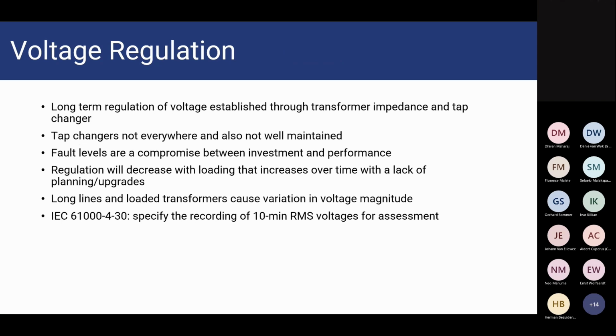Now, voltage regulation is the long-term regulation of the voltage established through transformer impedance and a tap changer. Tap changers are not everywhere and also not well maintained. And what also plays a big impact on your voltage regulation is the fault level at the point of measurement. And that's normally a compromise between investment and performance. So what do I mean by fault levels? On a system with a high fault level, you normally have a lower impedance, and vice versa, a lower fault level will have a higher impedance. So for a current that's being drawn over an impedance, the larger that impedance is, the bigger the voltage drop will be and the bigger the impact it can have on your voltage regulation.